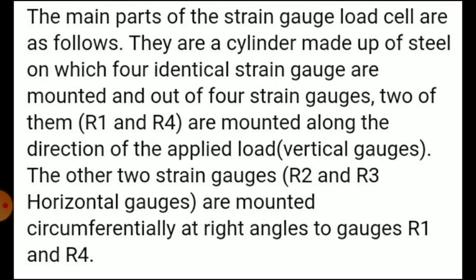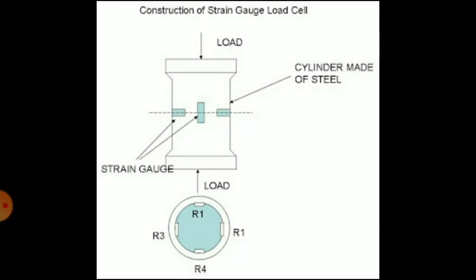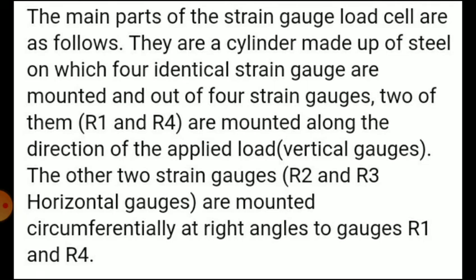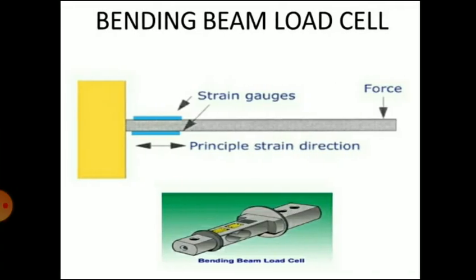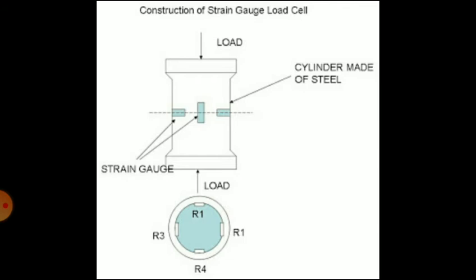The main parts of the strain gauge load cell are a cylinder made up of steel on which 4 identical strain gauges are mounted. Out of the 4 strain gauges, 2 of them, R1 and R4, are mounted along the direction of the applied load, that is, vertical gauges. You can see R1 and R4 in the top view, attached in a vertical direction. The other 2 strain gauges, R2 and R3, which are horizontal gauges, are mounted circumferentially at right angles to gauges R1 and R4. You can see R2 and R3 in a horizontal direction.